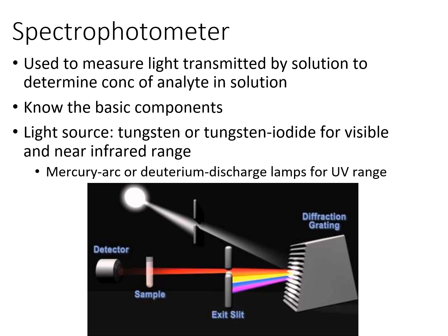Then we also have a cuvette, which is the sample holder that holds the solution. It must be transparent at the measurement wavelength, that way it can't interfere with the detection. And then we have a detector, which measures transmitted or absorbed light intensity. And then we have a readout device, which displays results, which is the absorbance or the percent transmitted.